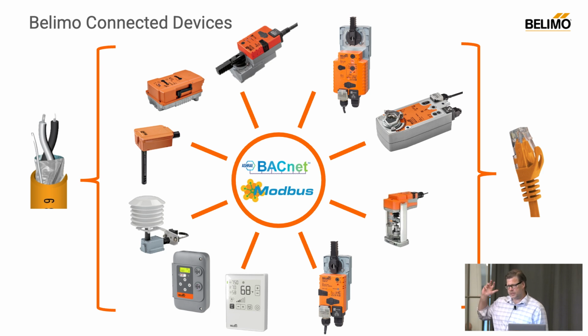All right, so on the right side, these are the IP connected devices. So this is BACnet IP and Modbus TCP. Same layout. These are both valve and damper actuators. We have some globe valves, as well as both versions of fail-safe, spring and electronic.